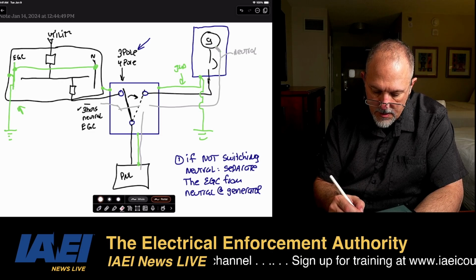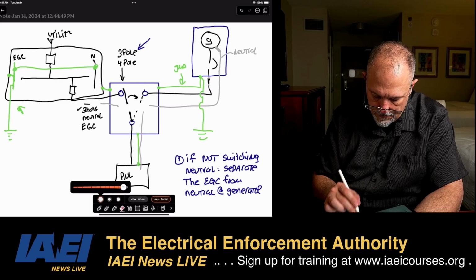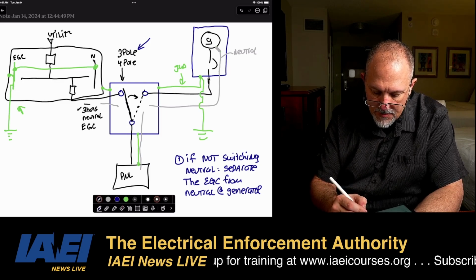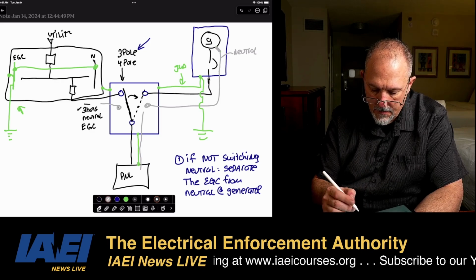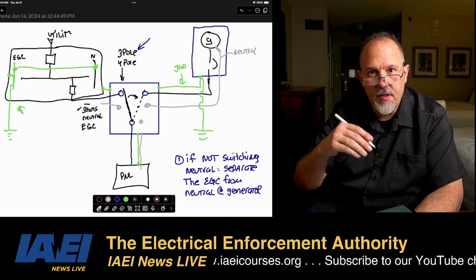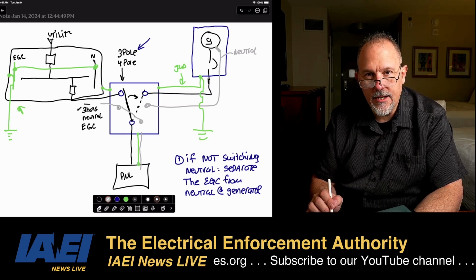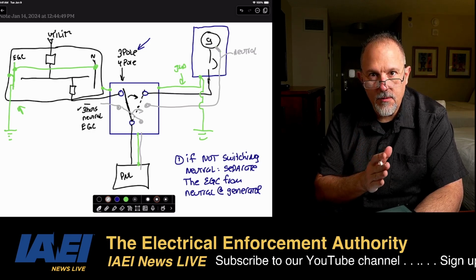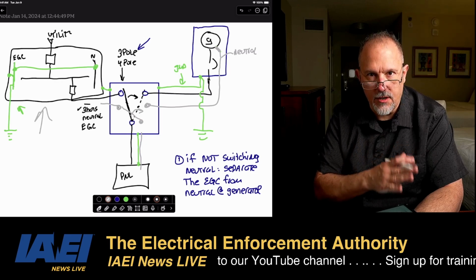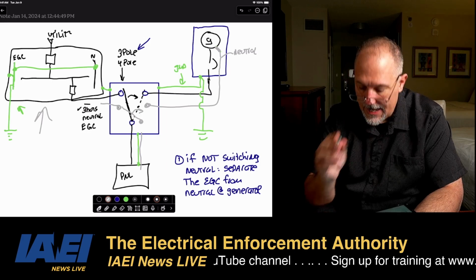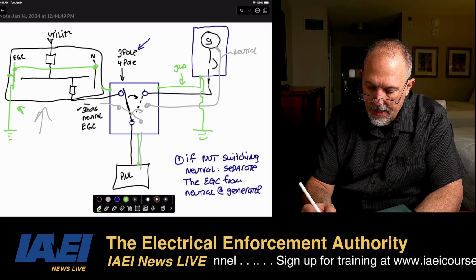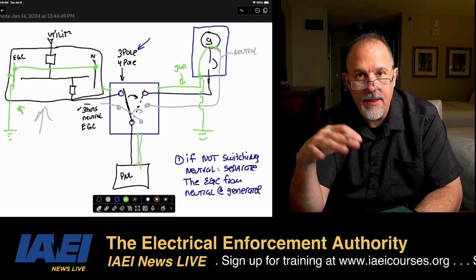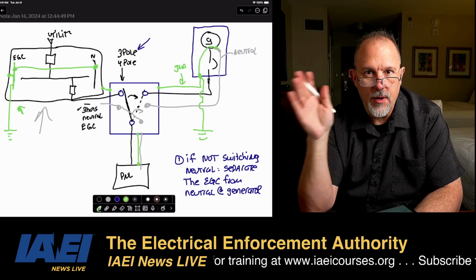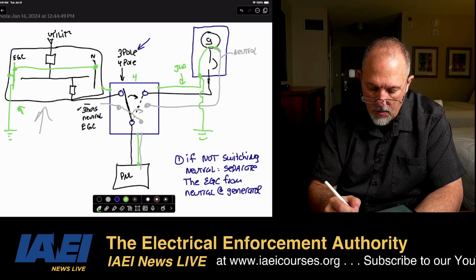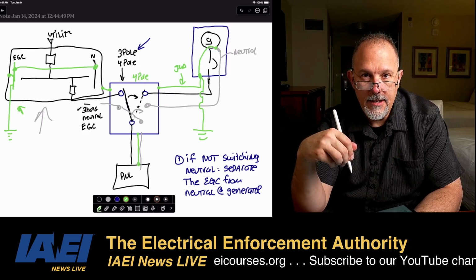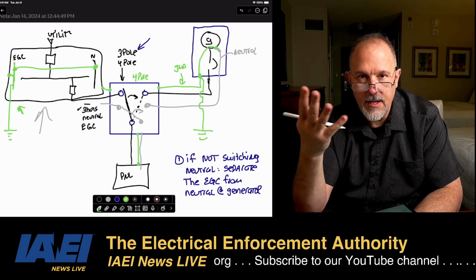If I'm breaking the neutral, so let's say that I do this, I'm breaking the neutral. All right? So now I'm switching the neutral. So along with the hot conductors, I'm also switching that neutral conductor. Now, when I switch over, all of this bonding that occurred over in the service equipment is no longer a part of the system. Now you have to make sure that you have a bond between the equipment grounding and the ground rod that you drove out there at the generator and your neutral in the generator. And that would mean you have a 4-pole generator, or a 4-pole transfer switch that is switching that 4th pole, which is the neutral. The three, so if this is a 3-phase, the 3 hots and the neutral.